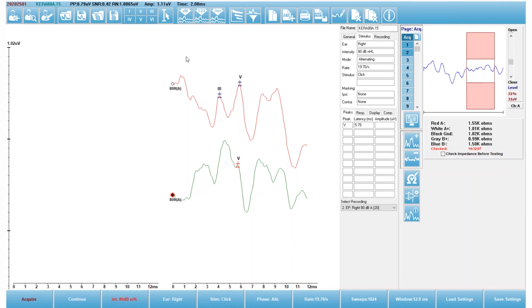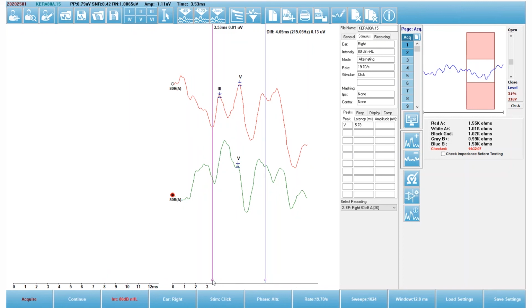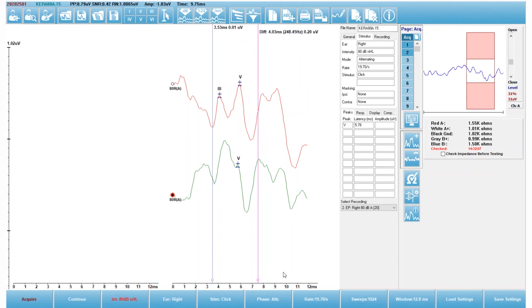Now, one of the things that you can do is add cursors to the screen. So I'm going to select the cursors, and then I'm going to drag them over. There's 2 of them. One is in hot pink, and then the other one is in blue. So it'll vary depending on which one that you're moving. And to quickly get a correlation coefficient, which is a comparison of the 2 waveforms as far as how close they are or how alike they are, I'm going to press the Control key and the handle to the right above the intensity. So here you can see I have 2 waveforms selected.